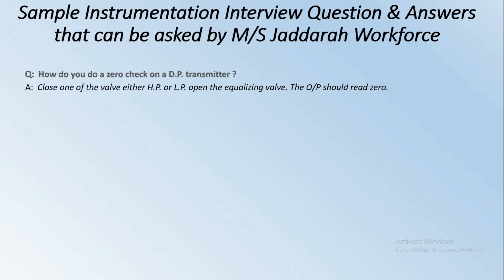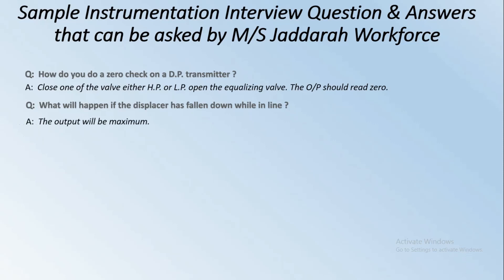Next: How do you do a zero check on a DP transmitter? Close one of the valves — either HP or LP — and open the equalizing valve. The output should read zero. Next: What will happen if the displacer has fallen down while in line? The output will be maximum.